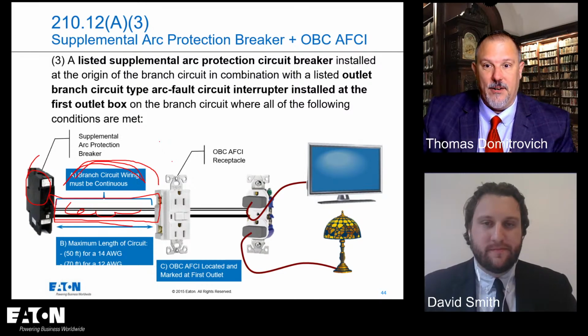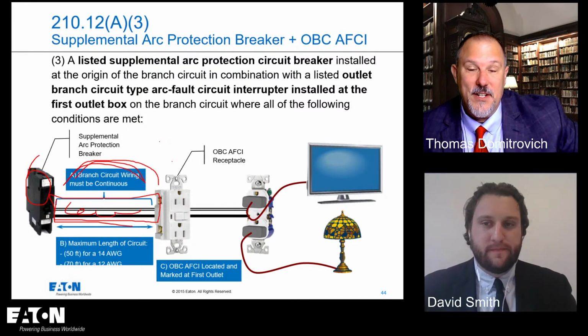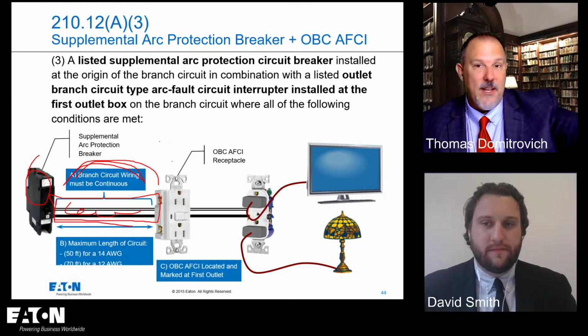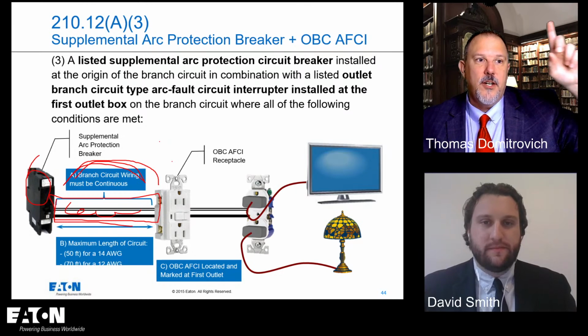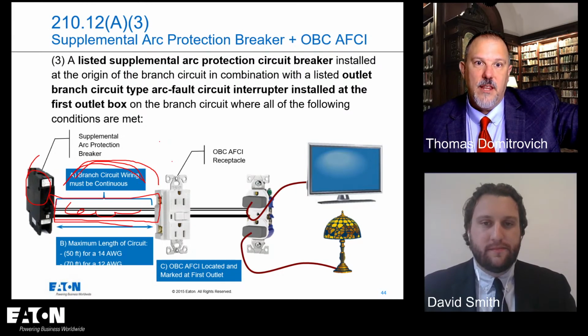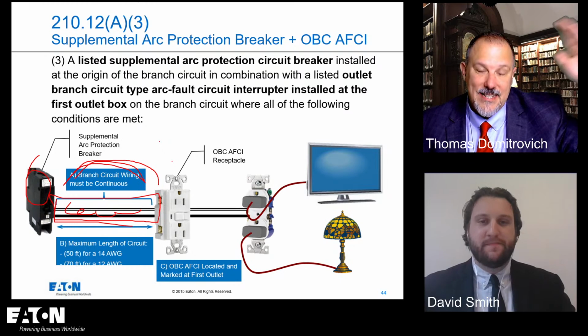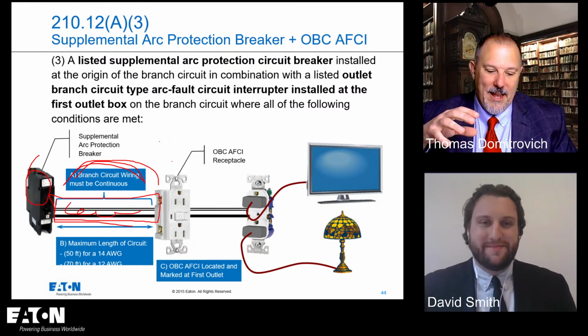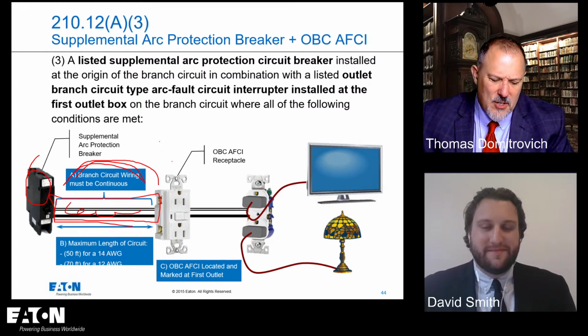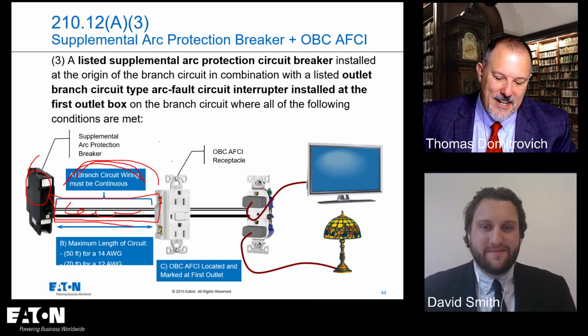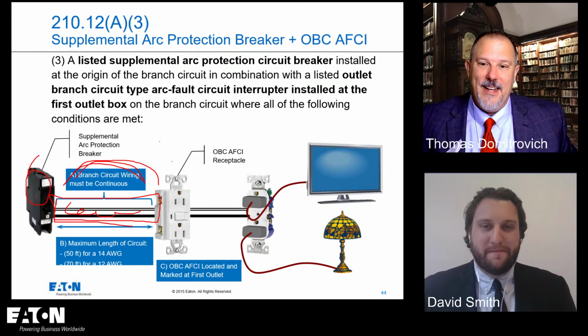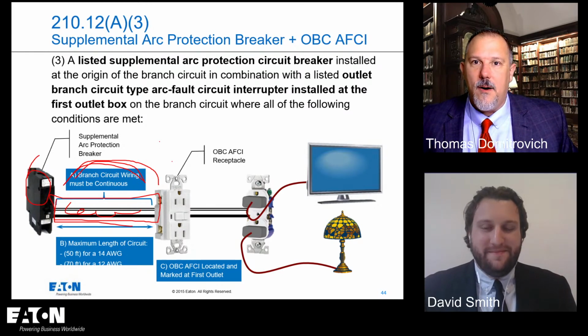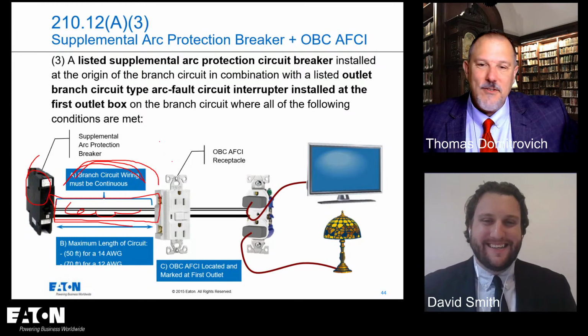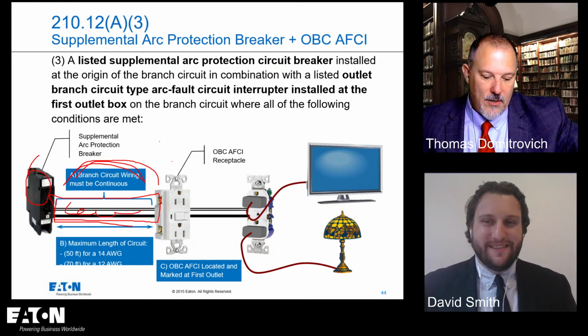And then you have sub panels. So it's not just the service. Like in this house here, I have a panel board in my basement, and I have a panel board upstairs in my bedroom. So the panel board, that conductor length is going to knock down the fault current at the secondary sub panel. And that all came up in the debates. We were looking at the reports and the studies, and we were like, okay, I had a Parks and Associates study, which was really good, but it didn't look at sub panels at all. And we're like, okay, well, the fault currents that you're finding is not quite on the mark.